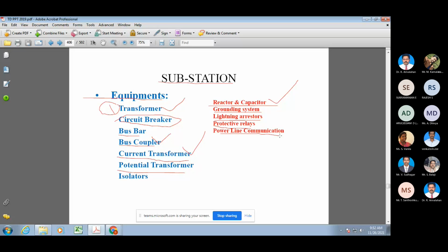We already saw the primary and secondary equipment. The first equipment is the transformer, a static device that transfers power from one circuit to another. It may be a step-up transformer, step-down transformer, power transformer, distribution transformer, or auto transformer - these are the different types. The second element is the circuit breaker, third the bus bar, fourth the bus coupler, fifth the current transformer, sixth the potential transformer, and seventh the isolator. These are the different types of equipment used in the substation.